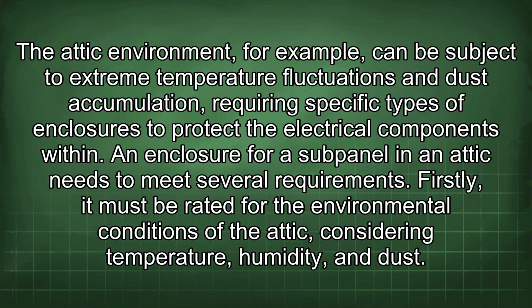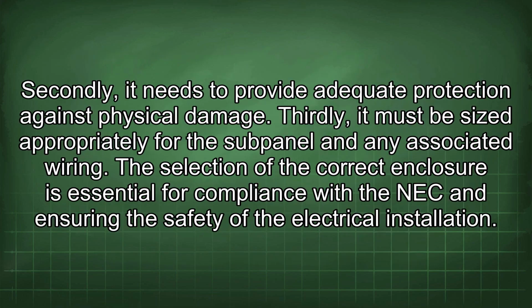The attic environment, for example, can be subject to extreme temperature fluctuations and dust accumulation, requiring specific types of enclosures to protect the electrical components within. An enclosure for a subpanel in an attic needs to meet several requirements. Firstly, it must be rated for the environmental conditions of the attic, considering temperature, humidity, and dust. Secondly, it needs to provide adequate protection against physical damage. Thirdly, it must be sized appropriately for the subpanel and any associated wiring.